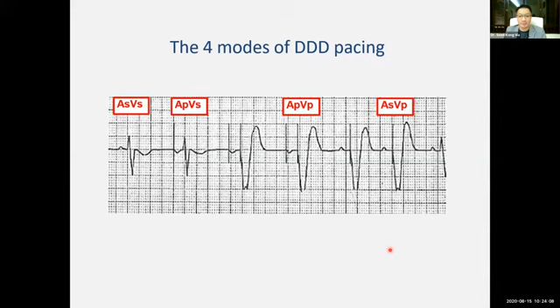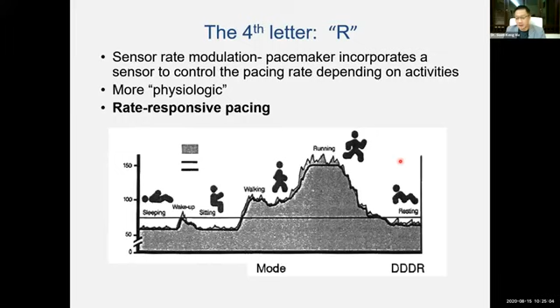The fourth letter here, the R, whether with an R or without an R, I shall not be able to go into too much because there are a lot of different technologies which are proprietary to different brands. But suffice to say that if you have an R, the pacemaker is a smart one. Smart in the sense that it can afford a more physiologic pacing experience for the patient, because R means rate responsive pacing. The rate that we set in the pacemaker will go according to the patient's activity. For example, if the patient is running, the pacemaker has a sensor, senses that the patient is moving, so it will pace the patient at a faster rate. So simply put, it is a smart pacemaker.